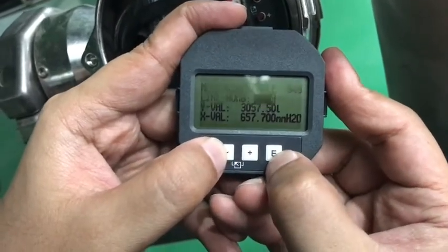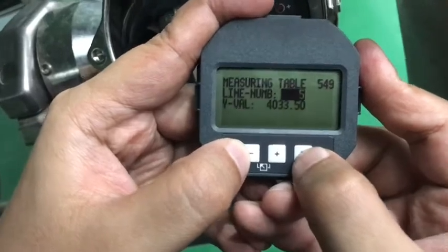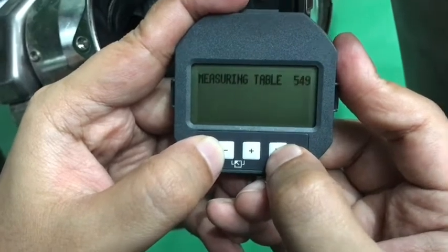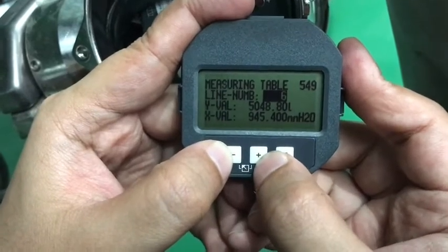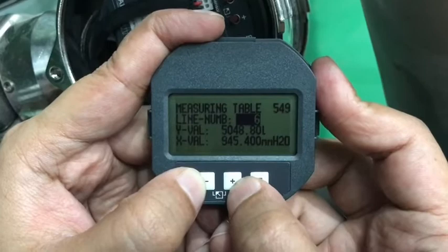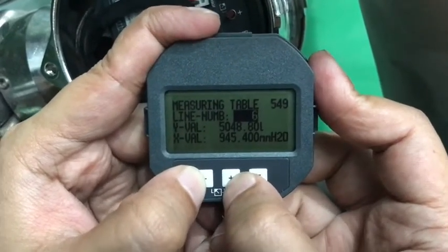According to that, you can set all values. The more values you insert, the more precise the reading it will give. Using this, you can set more than 32 values. Right now we have calibrated using a total of 10 values for 10 kiloliters — for each one kiloliter increment we put a raw value in here.